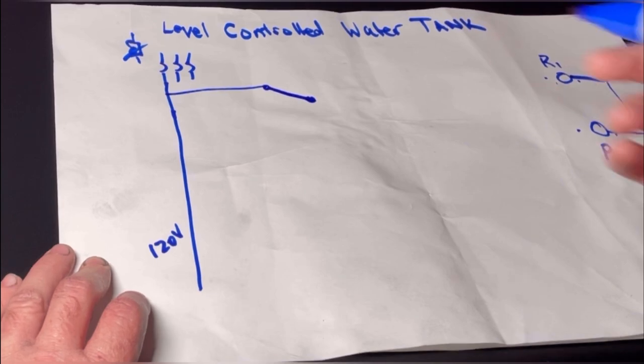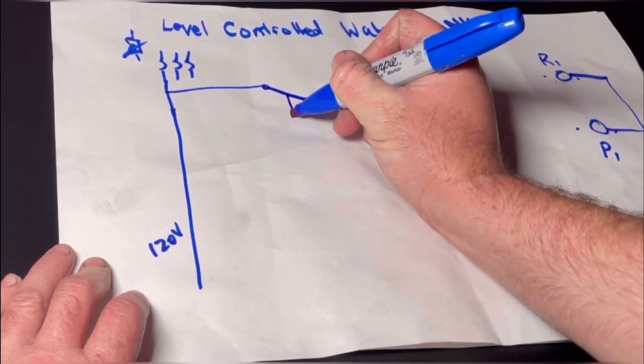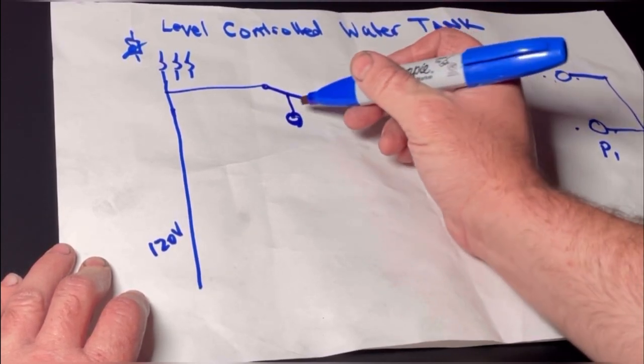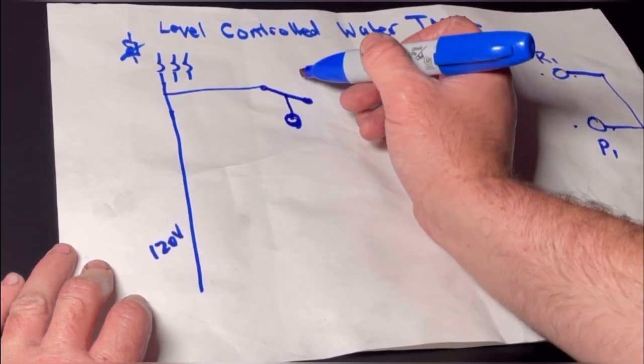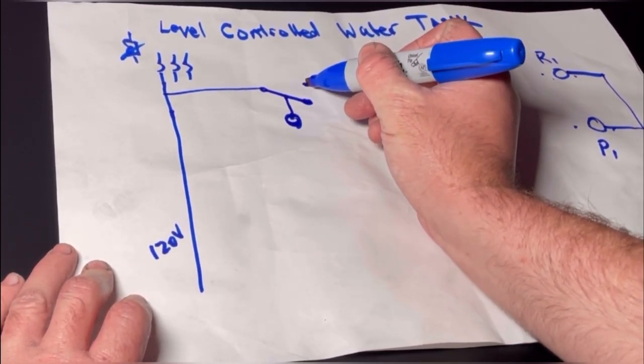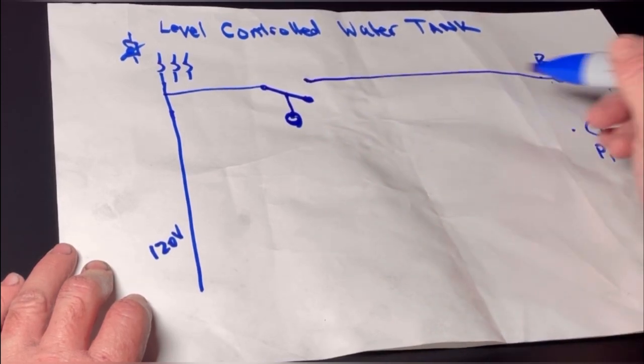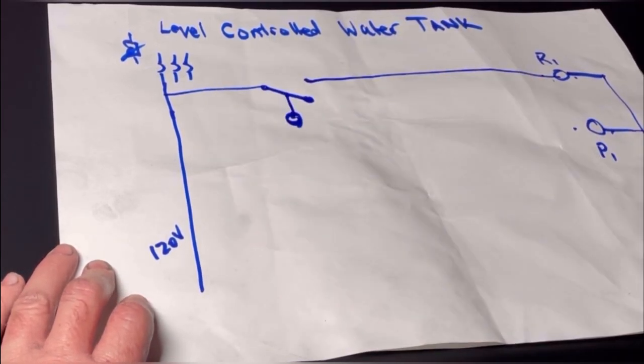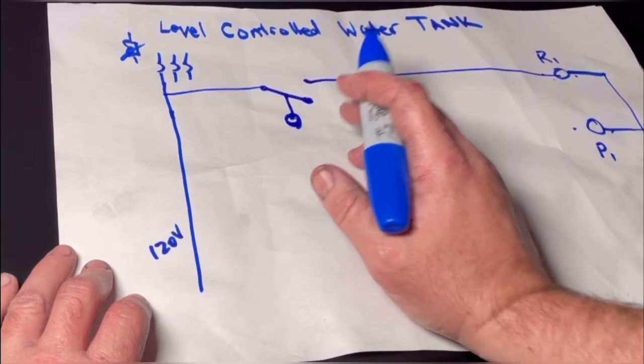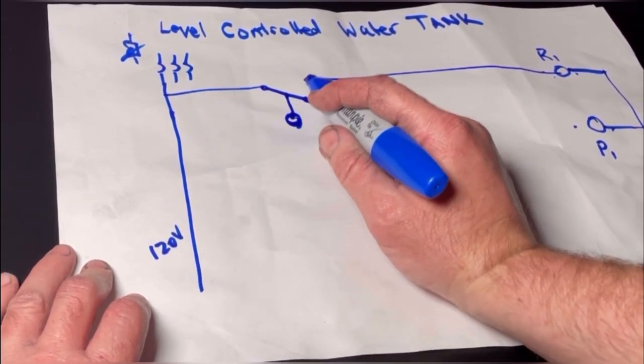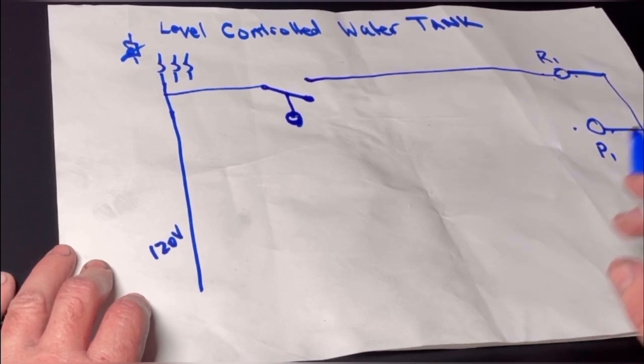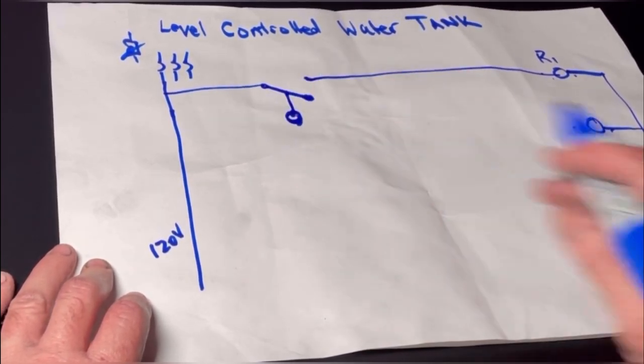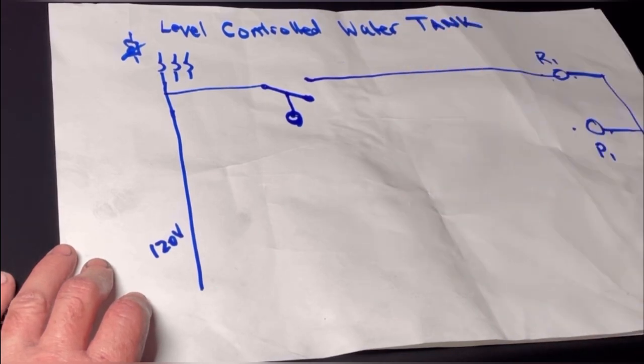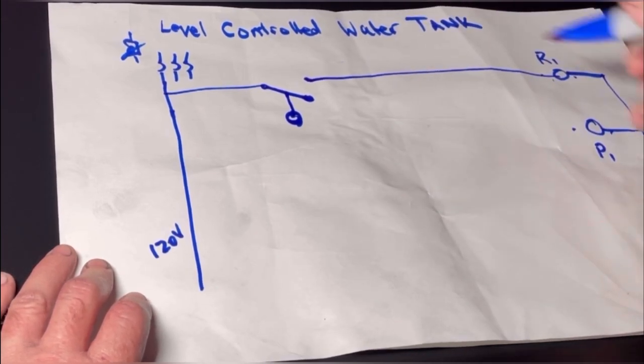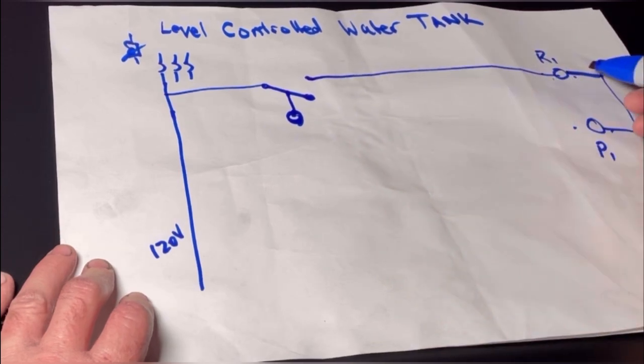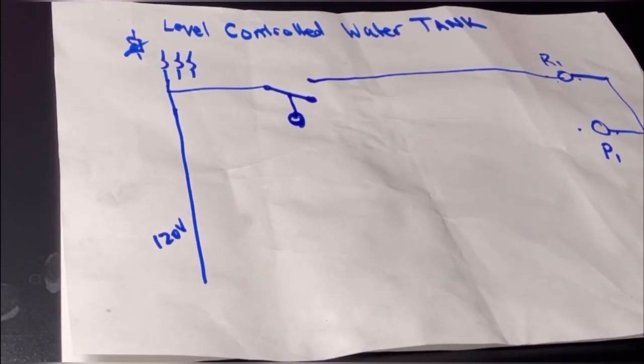Meaning that float switch is going to be sitting in the water, and when the water level comes up high enough, it's going to hit that float, close that circuit, and turn on relay 1. So we'll start with that, and then I'll demonstrate. You could go from the float switch right to pump 1, but that's probably not wise because these float switch wires are really small, and the amount of power that the pump consumes, the amperage, would most likely melt the wires. So I'll go ahead and demonstrate that for you guys now.